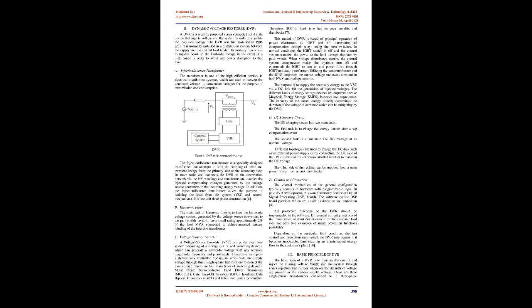2. Dynamic voltage restorer, DVR. A DVR is a recently proposed series-connected solid-state device that injects voltage into the system in order to regulate the load side voltage. The DVR was first installed in 1996. It is normally installed in a distribution system between the supply and the critical load feeder. Its primary function is to rapidly boost up the load side voltage in the event of a disturbance in order to avoid any power disruption to that load. An injection/booster transformer.